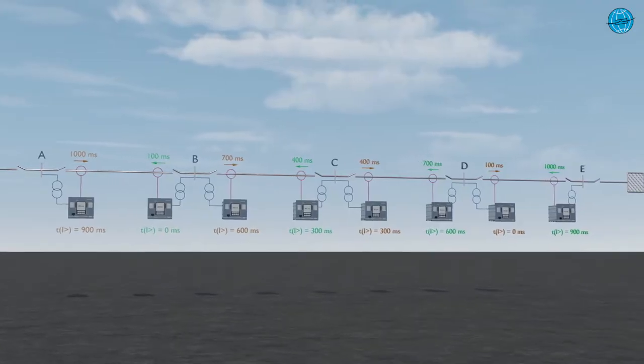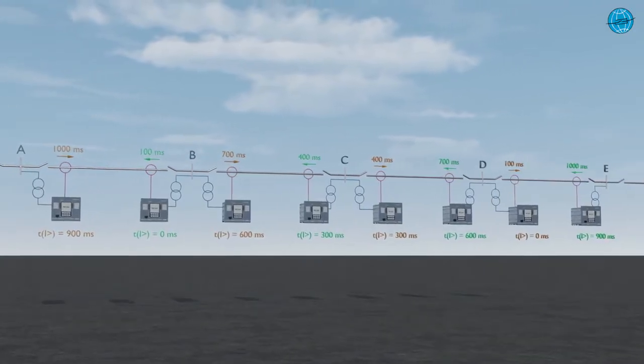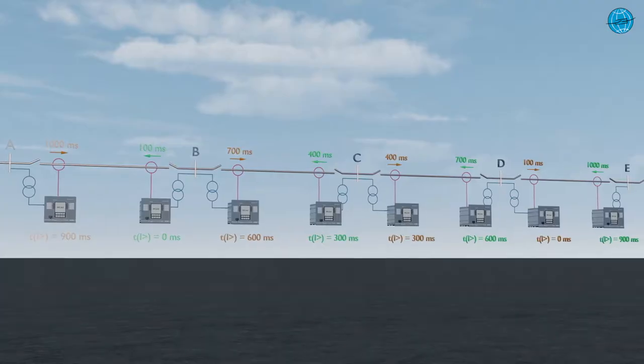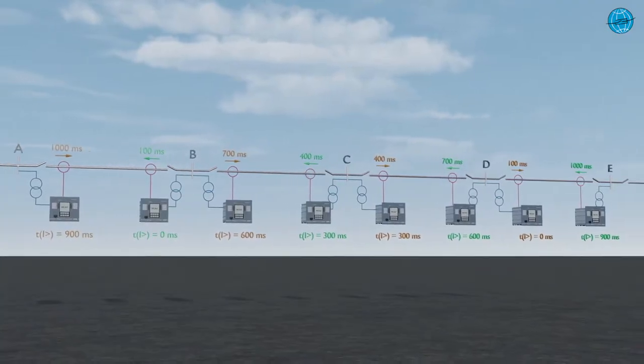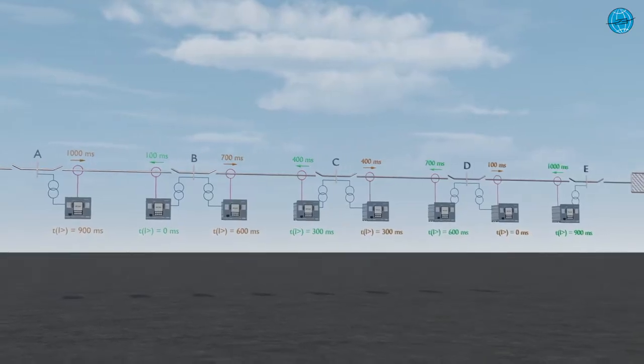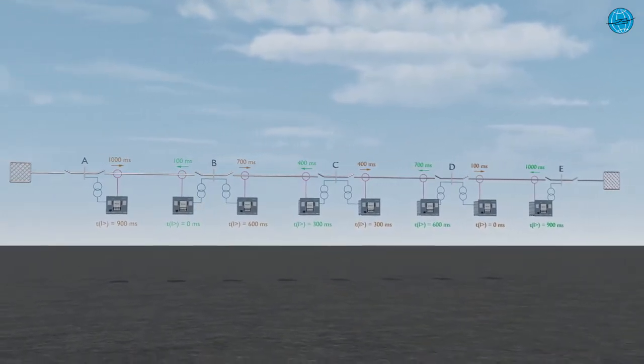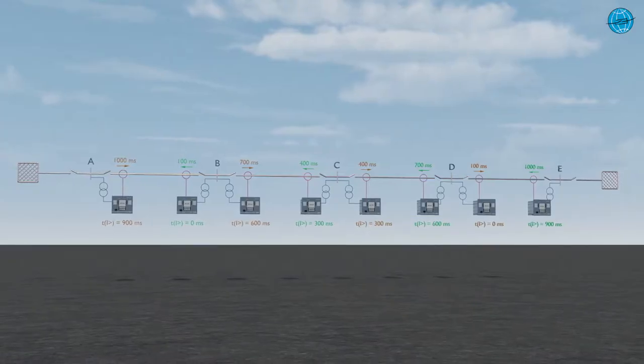And here, we can already see the main disadvantage. While the directional overcurrent protection can be set up easily and without communication connections, it already achieves fault clearance times of 1 second with 4 line sections. Further line sections cannot be protected with this concept. In addition, the longest fault clearance times also lie on the line sections close to the feeder, where the greatest short circuit powers are located.